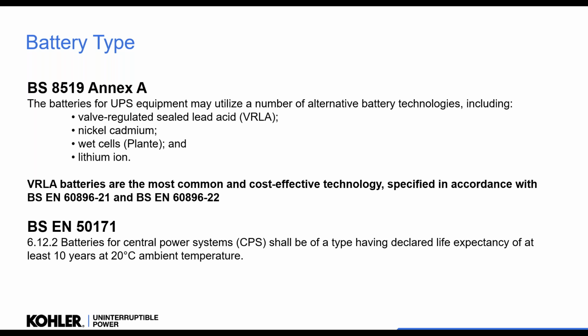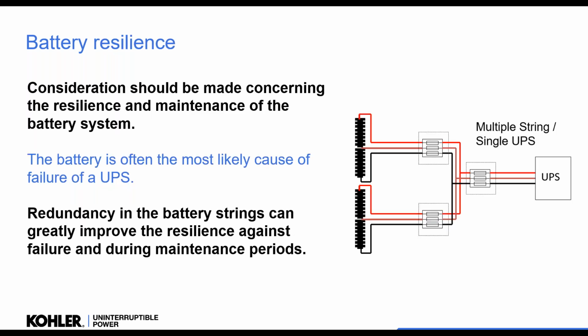It's much more cost effective over the lifespan and tends to be a more robust battery if you keep it at 20 degrees. Okay. Now the battery can be considered a weak point in any UPS system. Now most of the time it's only a weak point because it's not looked after, maintained, or tested. Okay, but we can improve the resilience of the battery by adding redundant strings. The HTM's guidance talks about this, having some extra resilience in the battery string.